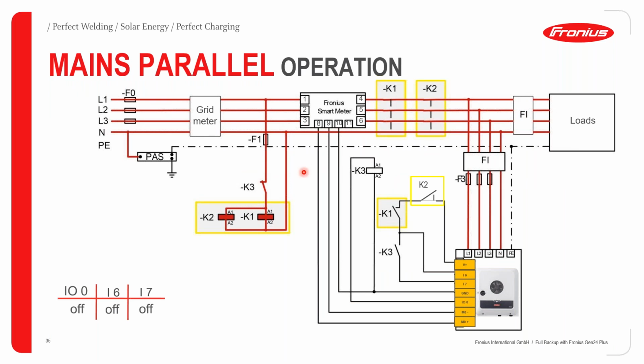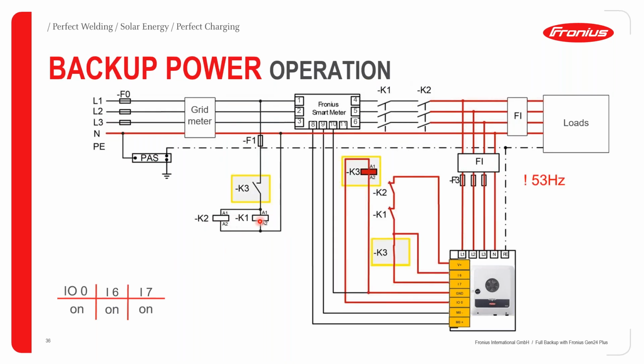So in the event of a grid outage, and before I go further, mind you, K1 and K2 are supplementary contactors which function in active redundancy mode. The coil is actually sourced from the grid, as you can see. So once the grid goes off, definitely K1 and K2 go off. Once they do, K3 comes into play and serves as the feedback input to the output ports, as you can see in this case. The normally open contacts of K1 and K2 now become closed and serve the input with 12 volts feedback voltage.